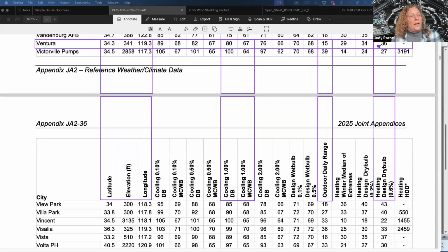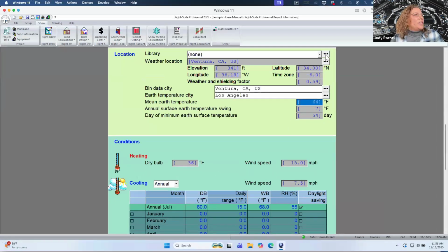So I compromise, and it's fully acceptable with any jurisdiction that tells you to use their conditions. It is absolutely acceptable by the procedures to use the jurisdiction having authority's guidance. So I take a look at what those conditions are, scribble all of those down for myself, and then go back to my load calculation and build a city starting with this as my basis.